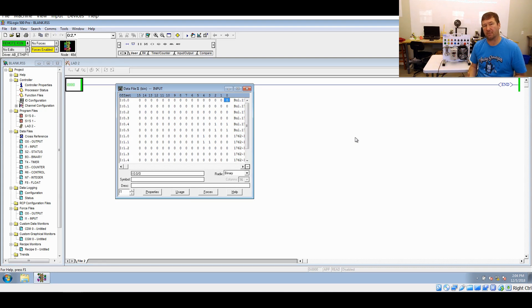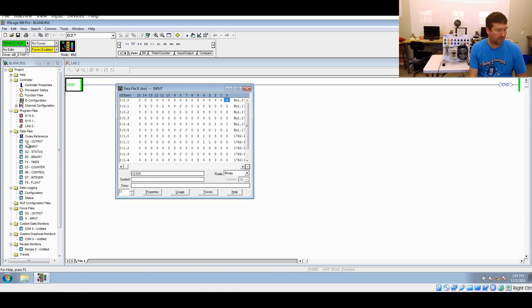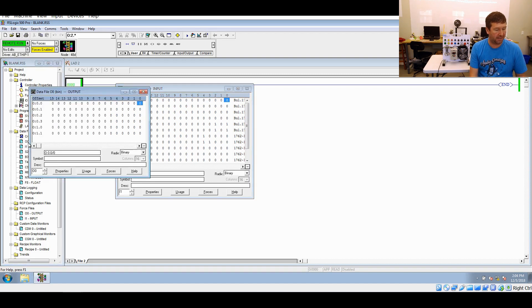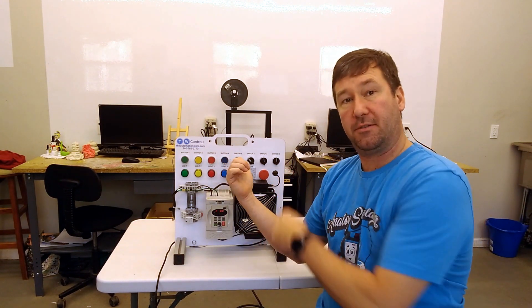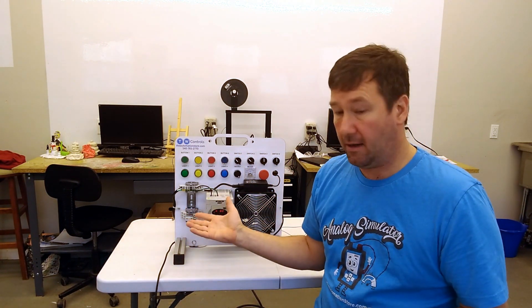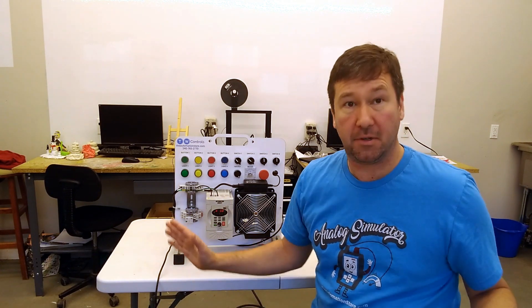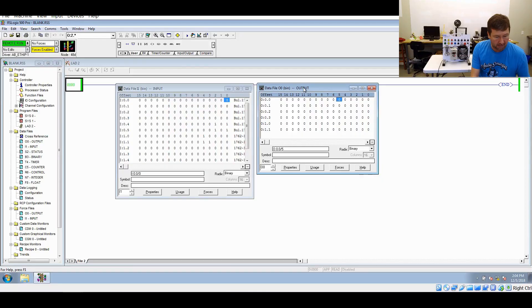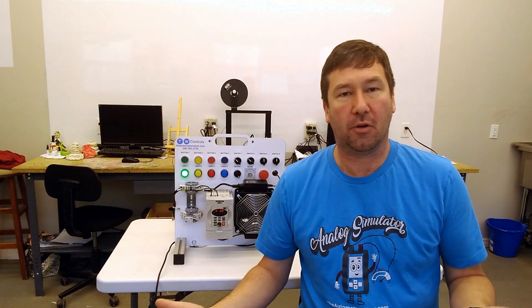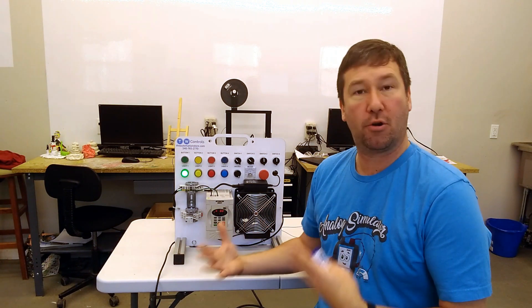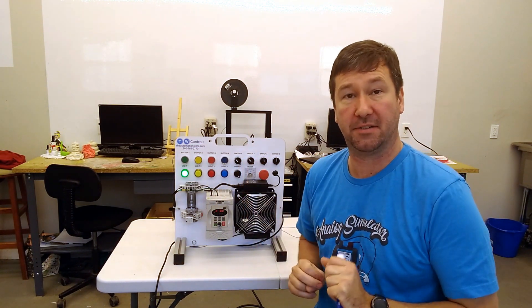So we can show an input status. Can we actually control anything from an output? Let's find out. Leave that data table open and let's go back over here under data files and double-click on our output data table. Same as the input data table, output zero through five on the PLC. We have output zero wired to our green light. Now we have no program — this is a blank program. But if we go manually into that data cell and enter a one, you can see that our green light turns on. Even an empty PLC program is still doing what we call a PLC scan.